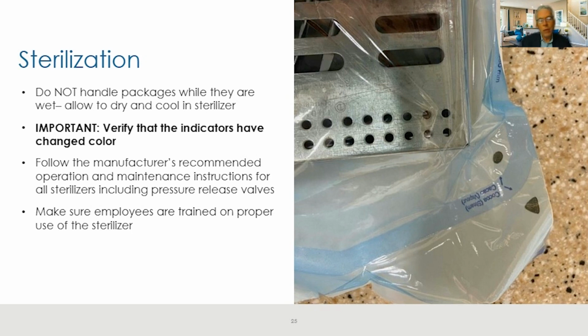Always make sure, too, that for the autoclave you're following the manufacturer's instructions for use. We happen to have Midmark autoclaves, and we have the instructions for use printed out - that's part of our training, how to properly clean them and how to maintain the pressure release valves. These are things that make these high-tech machines last longer. So make sure training on autoclaves is part of your protocol - don't just turn people loose with these machines.